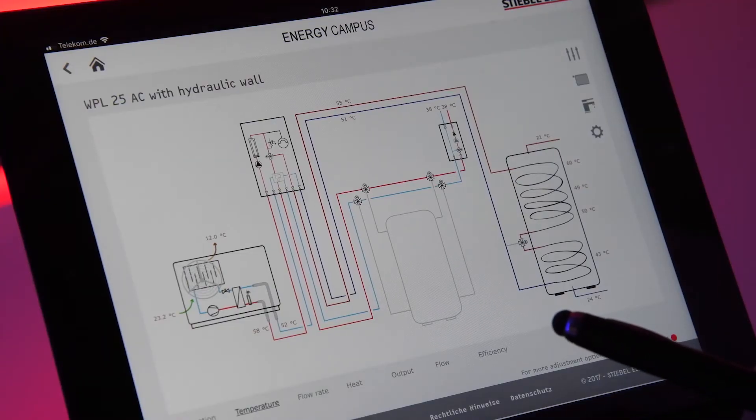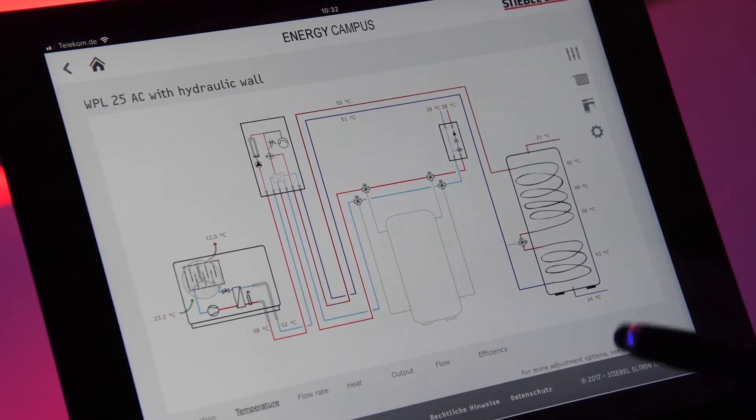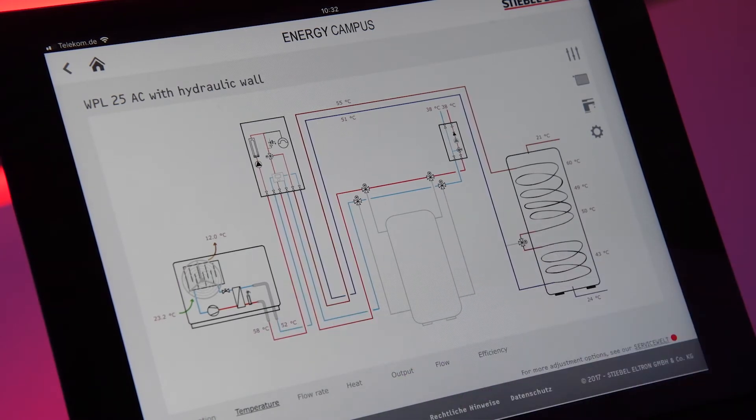And here we have now a heat pump running with a small capacity, 6 to 7 kilowatts, and you see here the flow and the return temperature from the heat pump has a delta T of 6 Kelvin at the moment.